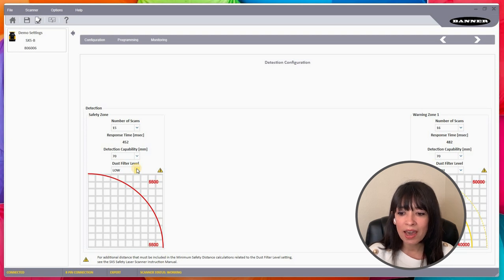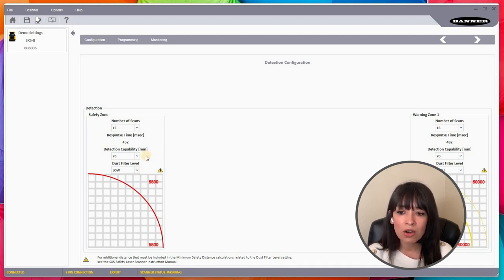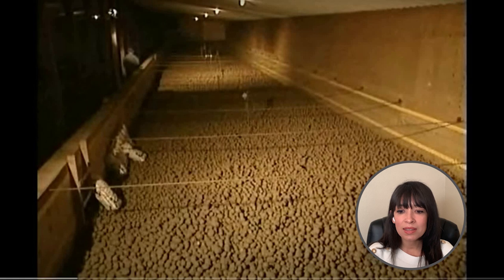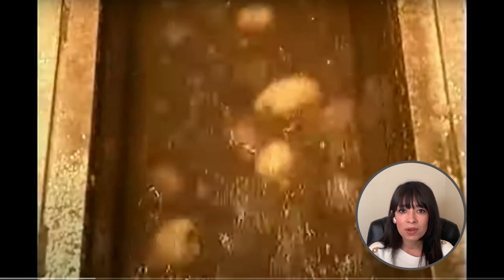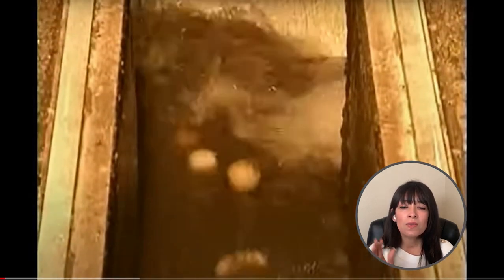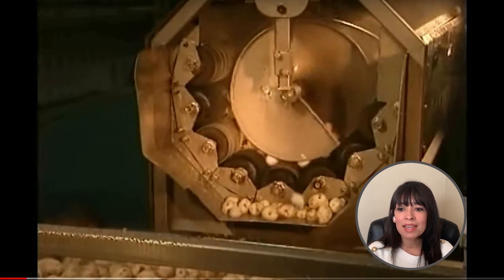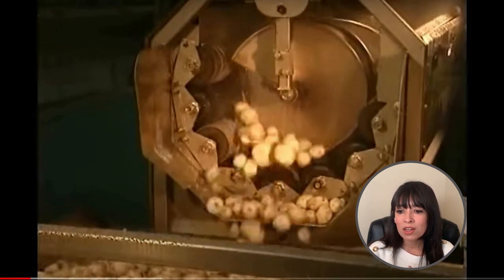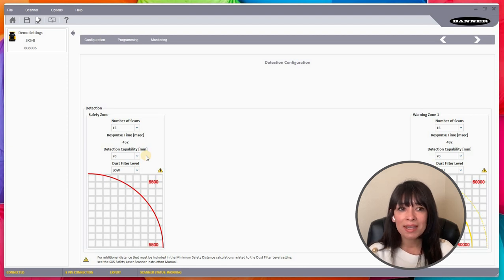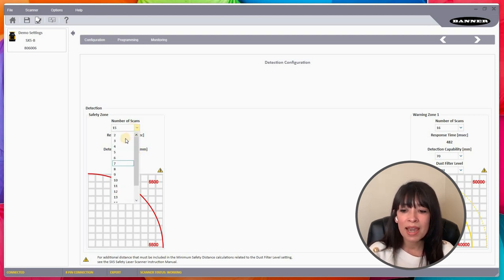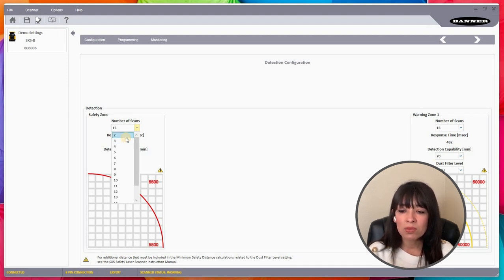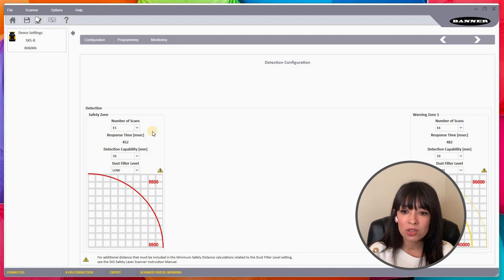There's a really cool dust filter feature that we have. You can set it to low, medium, high, and this really helps obviously for dust and just particles in the air. That really helps overcoming challenging applications. We had one application one time for a potato chip company. They wanted to make sure that they weren't going to get any false trips for the safety scanner if a potato flew into that zone. Those kind of things are where we can apply these filters. As we increase the number of scans before it remains in that condition before it sends an alarm, this is where we played around with that, made sure the response time was within the right tolerance, and we were able to get rid of those nuisance alarms that sometimes trigger safety outputs to turn the machine off.